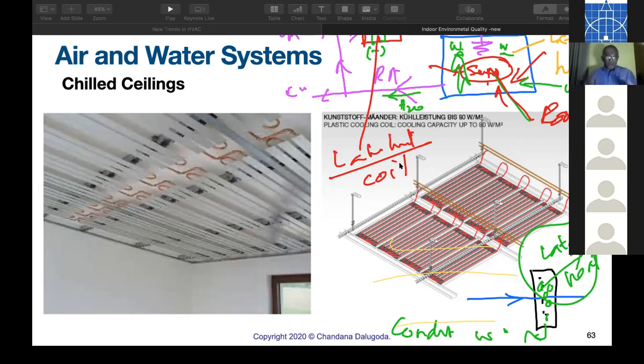Why am I telling you this? Every air conditioning machine, we must have positive return back to the air handling unit. So every time we should emphasize, we must have a return air duct. If the supply air fan cannot tackle it, have a return air fan as well.